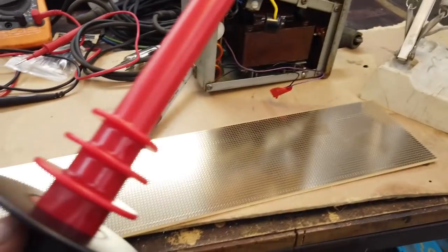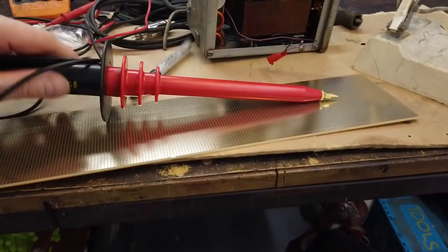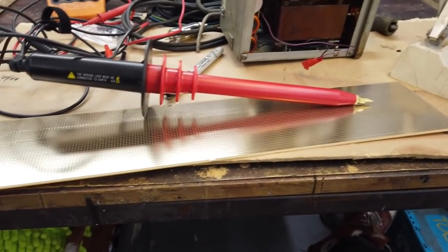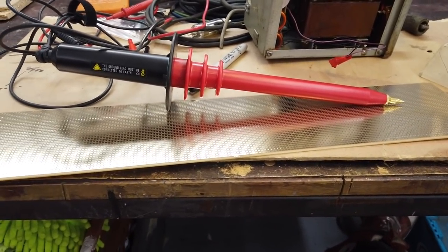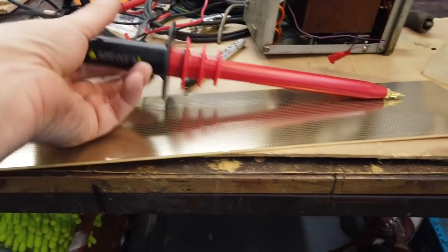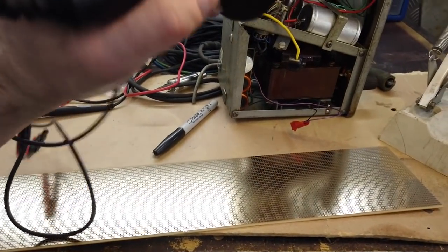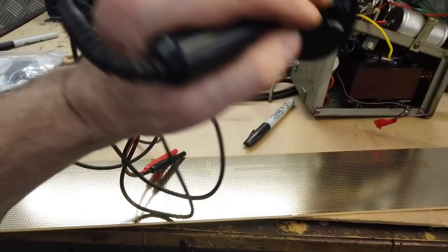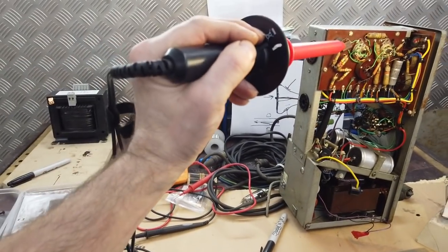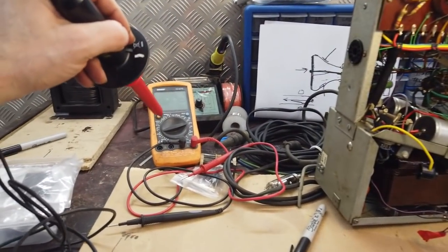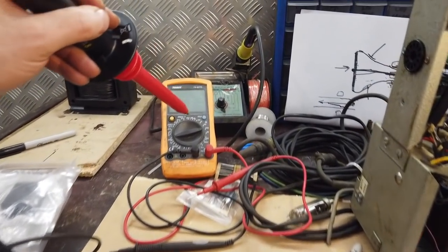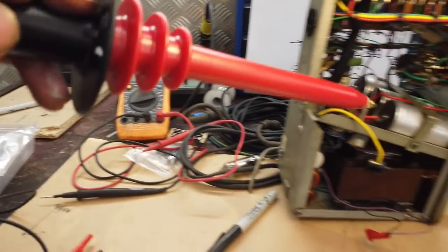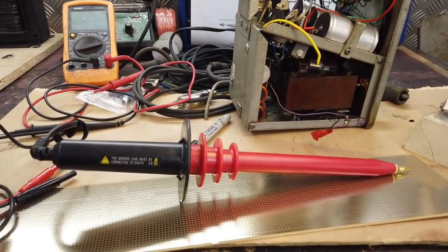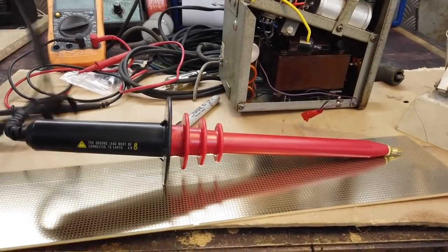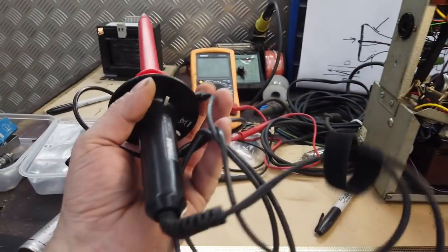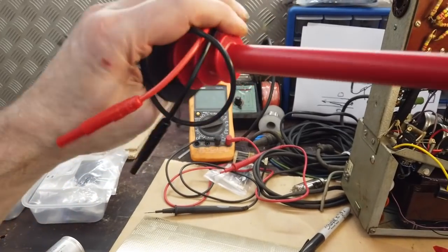So this probe, it's one of the ones we used to use. Well, not this exact model, I used a similar one. I had to leave it at work when I left the company. We used to touch this onto the high voltage parts, and you were completely safe because you were nowhere near. It gave you confidence to test. That reduces the reading on your meter by a factor of 100 or 10, depending. So your meter could then display the high voltages without having to get special high voltage meters, which were very expensive. So that's our high voltage probe, or sex toy, depending on how you want to look at it.